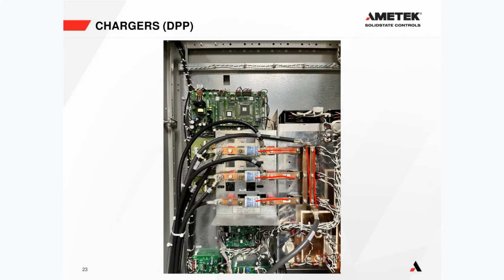And it's this control board here, this is PCB1, there's a sticker that says PCB1. This is our rectifier charger interface board, the brains that tells the SCRs when to fire. Also, a little hidden here, this is the gate drive board, which gives isolation between the printed circuit board here, which is a low voltage board, and the gate drives to these SCRs on these terminals, which are connected to 130 volts. So the gate drive board gives us isolation, meaning this board does not see 130 volts. It also gives a bit of oomph to the signal we send to the SCRs to turn them on when we tell them to.